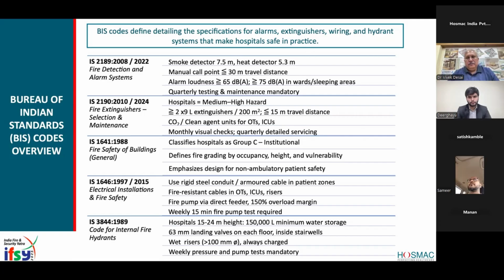So normally, if you see, in all the hospital buildings, people will put a pump, but it will not be a wet riser. It will be a dry riser. Wet means the water has to be filled into the entire system from the pump up to the terminal points of the sprinkler and hydrant. So normally people don't do that.